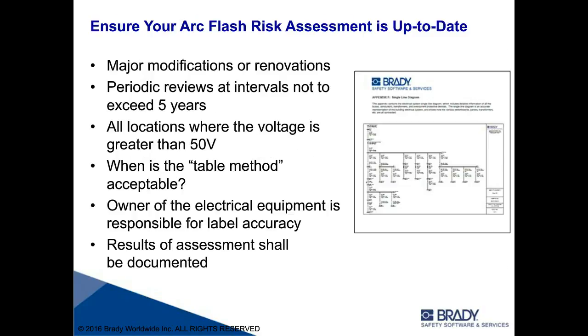So moving on, it's always important to make sure that your arc flash risk assessment is up to date. What NFPA 70E says is that anytime a major modification or renovation is done, you've got to update your arc flash risk assessment. If you do a major addition, that's pretty straightforward. You're going to be adding new equipment. It's not going to have labels. You've got to have that taken care of.